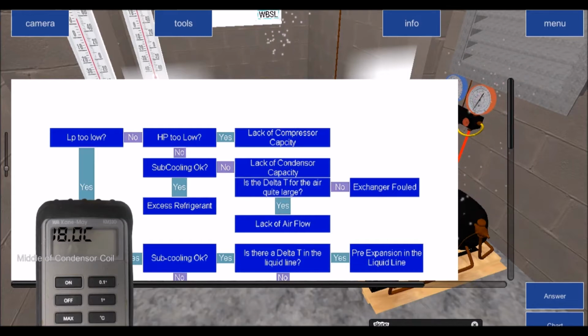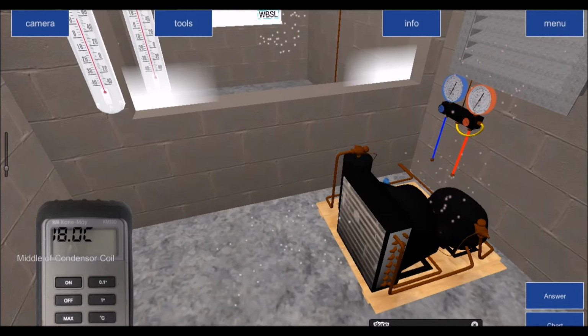In other words, what that means is that for some reason this compressor is not pumping properly. Now that could be from a cracked head gasket, it could be from a cracked or broken suction valve reed, it could be from a cracked or broken discharge valve reed. So there are numerous reasons why it's not pumping efficiently. It could be not because of the compressor itself. It could be because an accessory component that has been fitted to the system is allowing discharge pressure to enter into the crankcase side or the low side of the system.